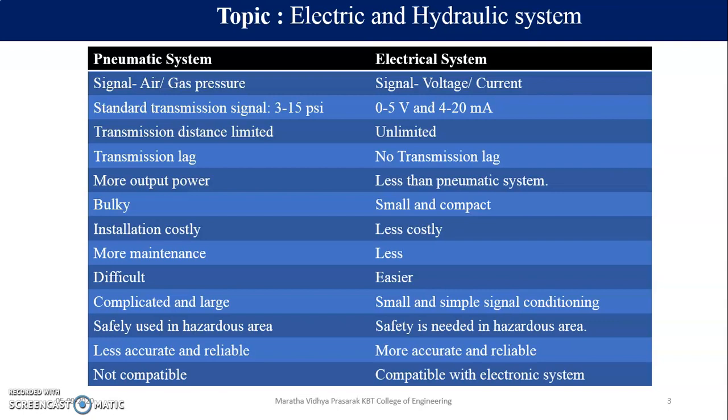So when we want to actuate any actuator using the pneumatic system, we should not take a distance which is very far from the standard transmission distance limit. Why is it important? If I want to do a punching operation, and my punching pressure is not proper, then the punching would not be of good quality. To avoid this, the distance should be limited so that there won't be a very high pressure drop when the signal is being transmitted to my instrument.